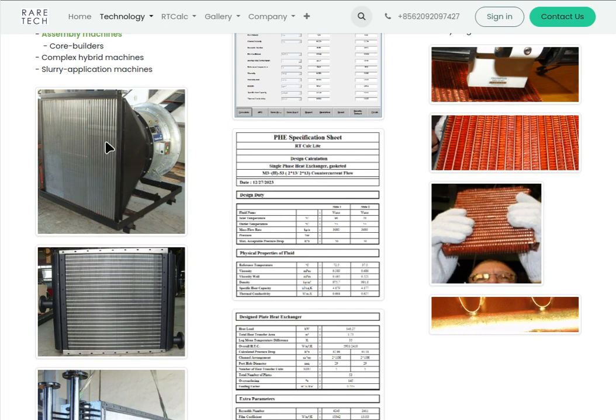What's critical with these things is the pressure drop. If you don't match the fan properly with the fin profile, the air doesn't go through the core properly, it just spins over and doesn't pass through, and it stalls. So the designer has to know how to couple the fan, get the spec right with the manufacturer, and be careful. I've seen people overdo it, pumping the motor too high so that nothing comes through the fins because the pressure drop through the fin is too high.